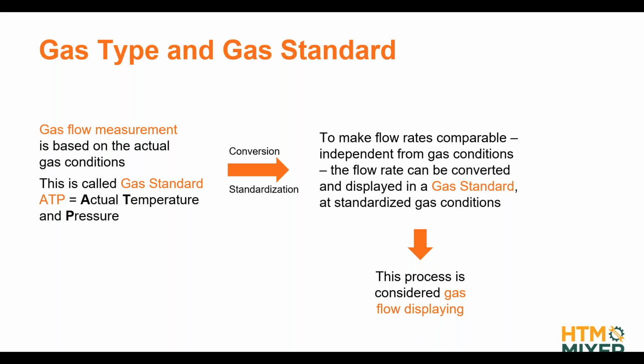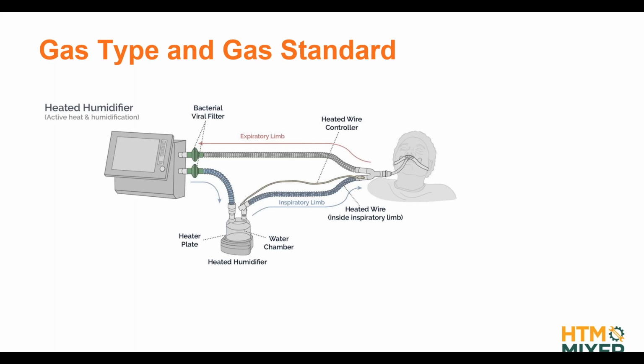So now you might ask, why the hell do we need to care about that, right? So now I'm going to talk about practical examples. I think that will make it much clearer. What you can see here on the screen is a typical setup of a ventilator on a patient. We have the ventilator here. We have an inspiratory limb, typically a heated and humidified inspiration limb. So we have a humidifier, and usually a heated wire inside your limb here to the Y piece, and then we have the interface to the patient, and then an expiratory limb back to the ventilator, right?